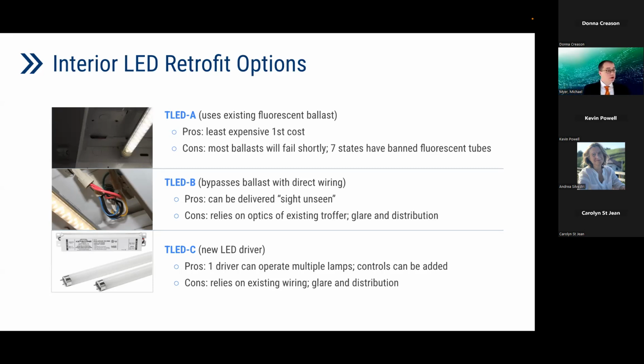A note of caution: because you are modifying this fixture in place, you should put, and it's actually required, a warning label on the type B and type C. The fluorescent ballast uses a different voltage, and by rewiring and getting rid of that ballast, you're now bringing in either 120 or 277 volts, which can create some problems.